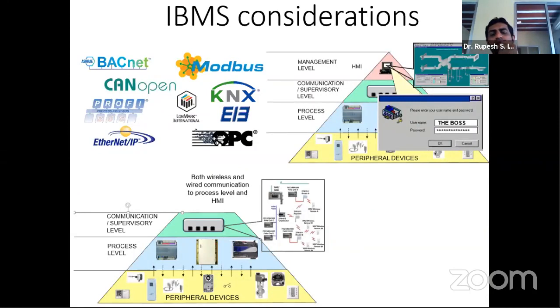And then coming to the integration part itself or the IBMS, where all of my systems will be integrated either on a free protocol or on a ubiquitous protocol or on an open network. I mean, BACnet has now taken precedence in becoming the most used kind of protocol. But of course, there is Modbus, KNX, Lonmark. Many of these protocols are there where we could integrate these systems. We have our peripheral devices talking to the process level, and then to the communication level, and then to the HMI itself, where we can actually monitor and control all of these systems.